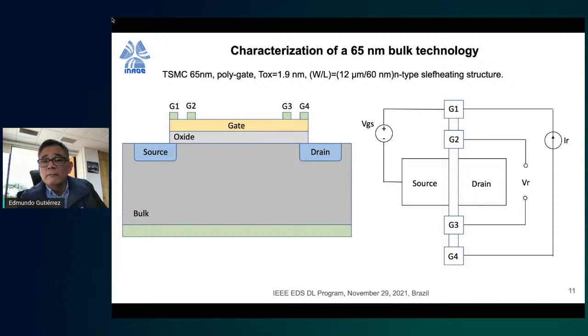We bias the gate by putting the voltage at the electrode G1, and then we flow a small current through G1, and then we measure the voltage drop through G2 and G3. By measuring that voltage drop, we are just characterizing the electrical resistance of this poly. The resistance of the poly is calibrated from room temperature down to very low temperatures.